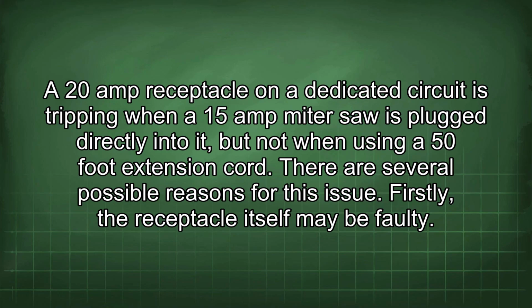A 20 amp receptacle on a dedicated circuit is tripping when a 15 amp mitre saw is plugged directly into it, but not when using a 50-foot extension cord. There are several possible reasons for this issue. Firstly, the receptacle itself may be faulty.